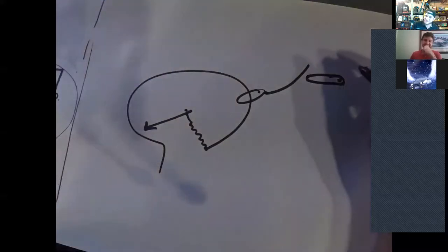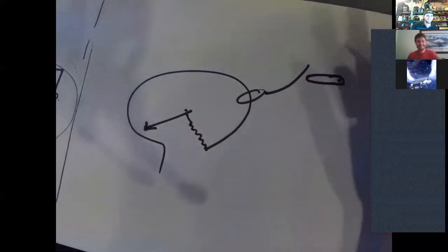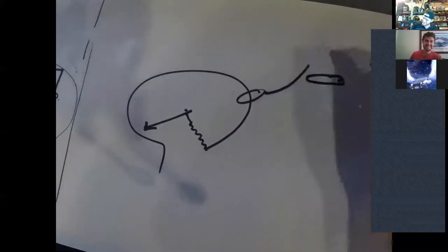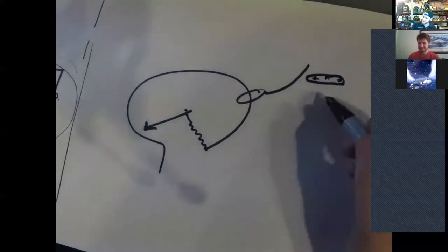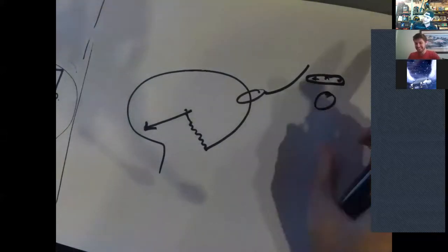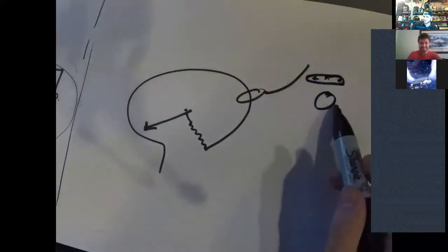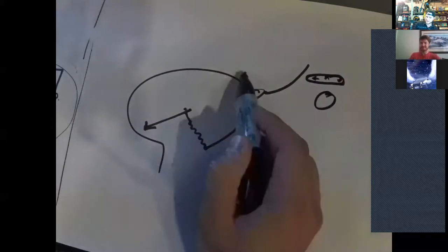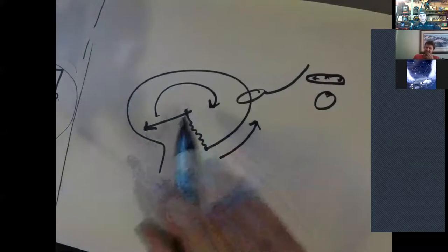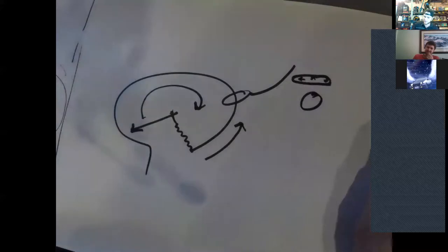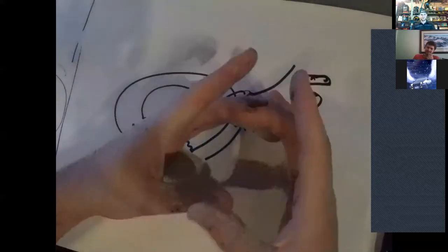So you got your shepherd's crook shaped Bourdon tube, your linkage to your pivot needle. And the cross section here is kind of ovular. And so if you increase pressure of your fluid, it's going to want to straighten or it's going to want to expand into a circular shape. And so that expansion just causes a straightening of this tube. It's going to pull on that linkage and your needle is going to spin.